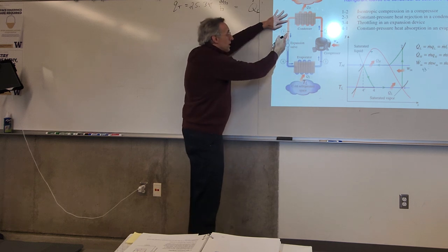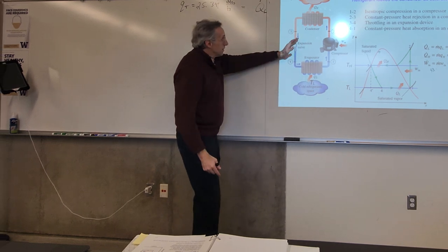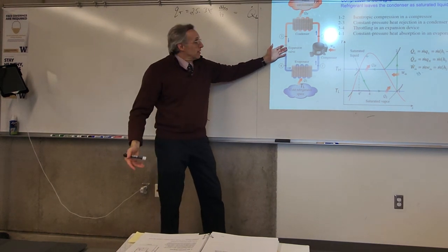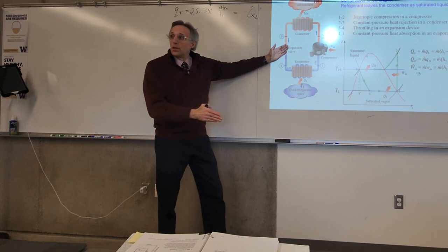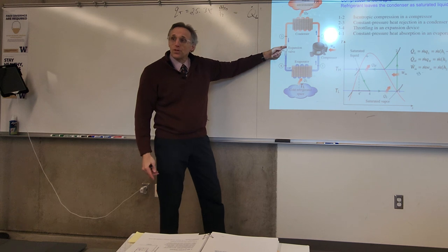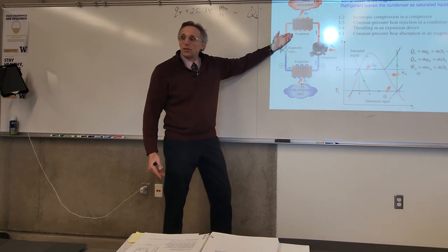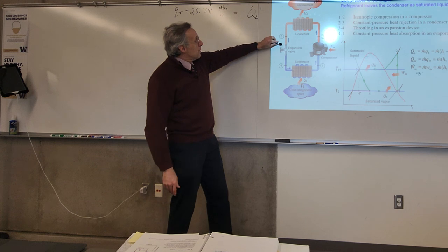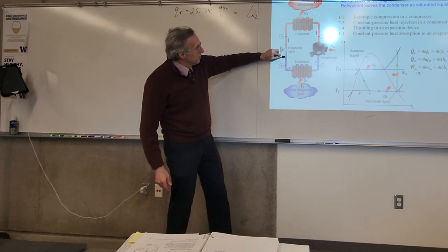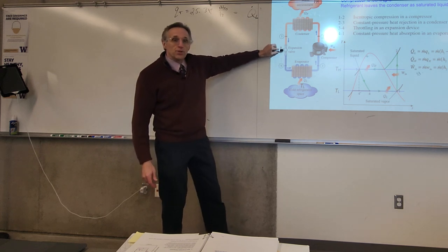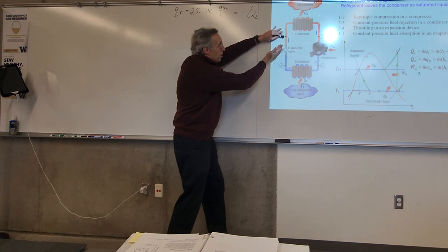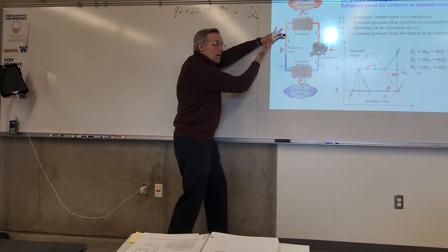And then we take this liquid and expand it, flash it through a throttling device that drops the pressure. We just kind of block the flow. It's like an obstruction, a controlled obstruction in the path of the refrigerant, so the refrigerant backs up. You create a little traffic jam of refrigerant molecules, so high pressure where the molecules are backing up, and then you're just letting a little bit through at a time here, so the pressure drops down low, and that drop in pressure causes a good chunk of this liquid to vaporize.